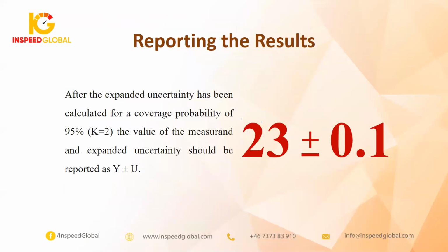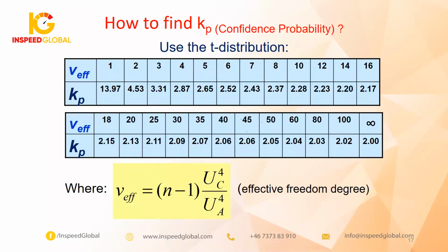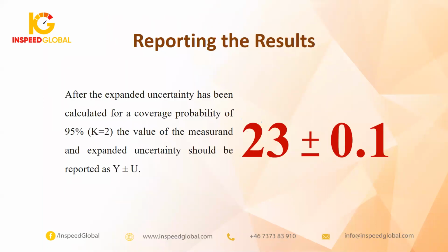The other point is how to report the result of uncertainty. How to report? If due to this equation we get an expanded uncertainty equal to 0.5, as an example, or 0.1 would be the same example here. 0.1. Your result is 23. Don't forget that your main result is the average. If you get 5 readings, the final result is the mean or average, 23 as an example, and you make this calculation to get the uncertainty, which is equal to 0.1. How to report this value?